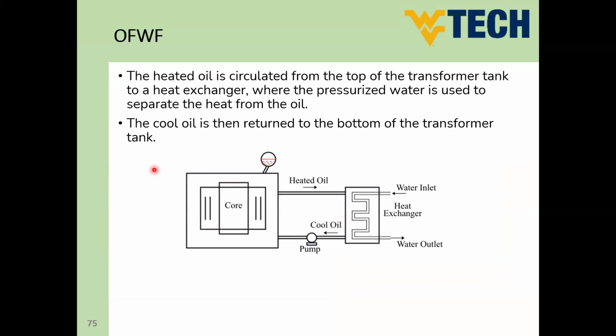If air is not sufficient, the next step is going to be water. The heated oil is circulated from the top of the transformer tank to the heat exchanger wall, where pressurized water is used to separate the heat from the oil. So the idea in the heat exchanger itself, guys, is that this is the forced oil. This is the pump used for the forced oil, and the tube to go to the heat exchanger. But here in the heat exchanger, instead of having air like the previous method, we have water.